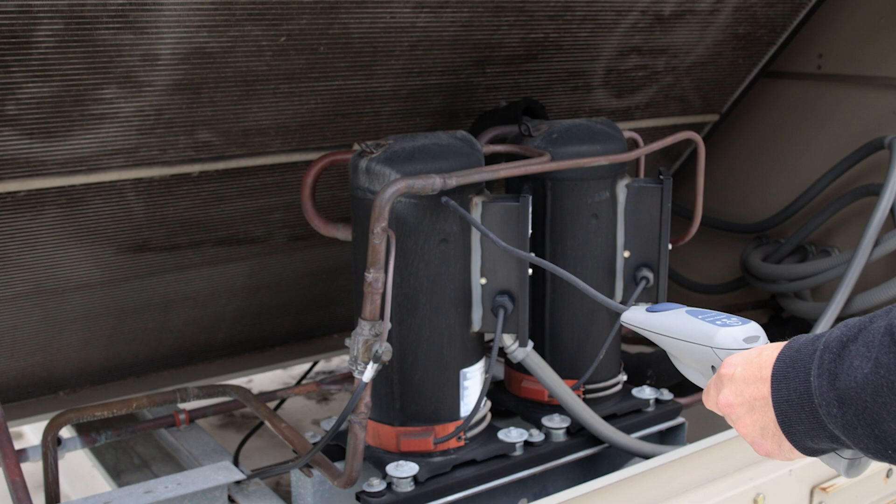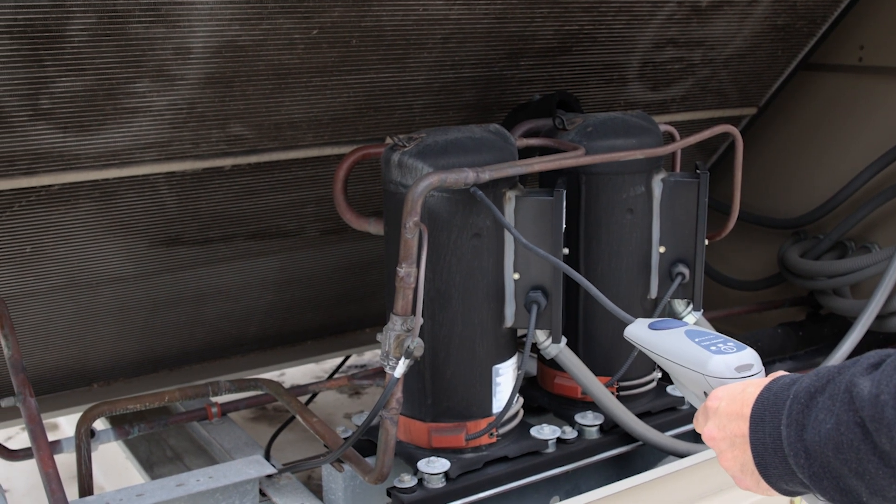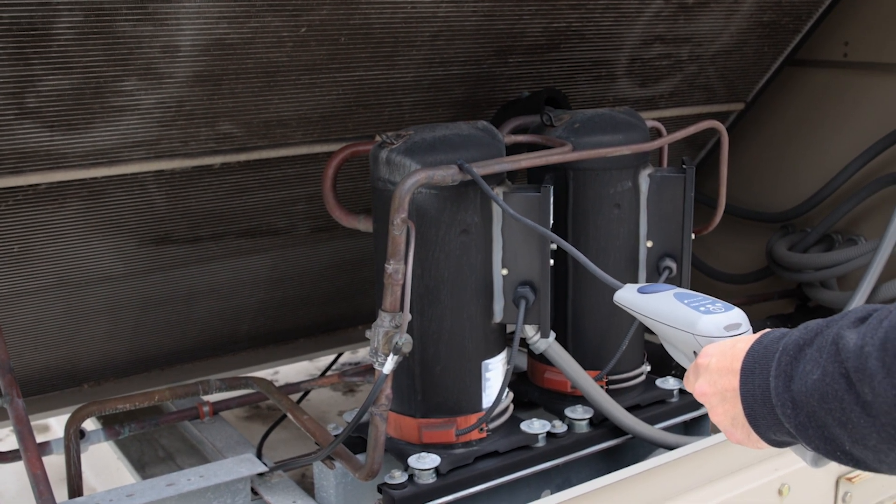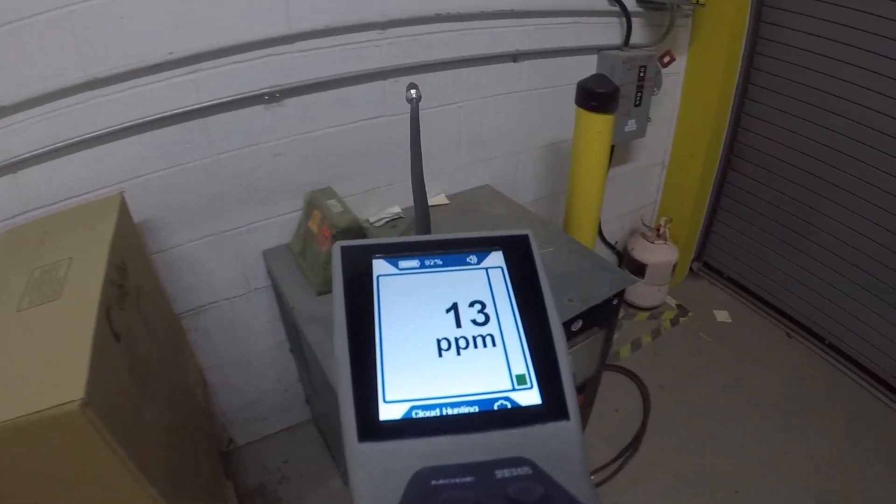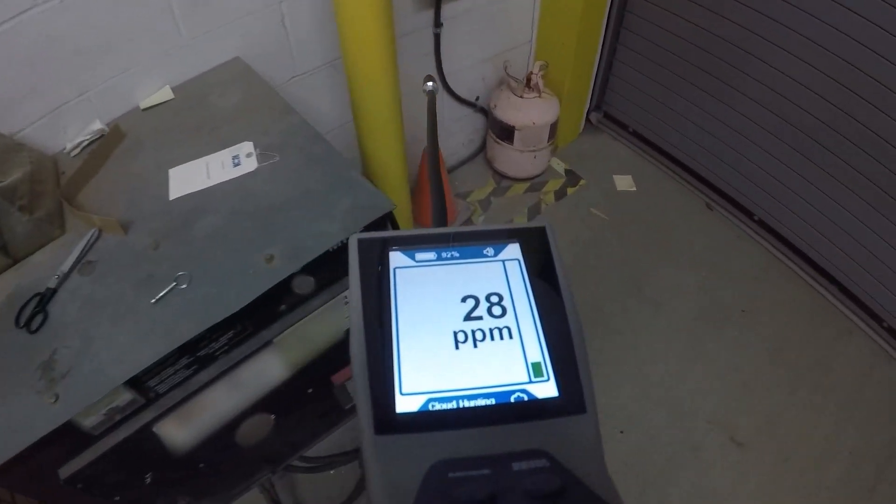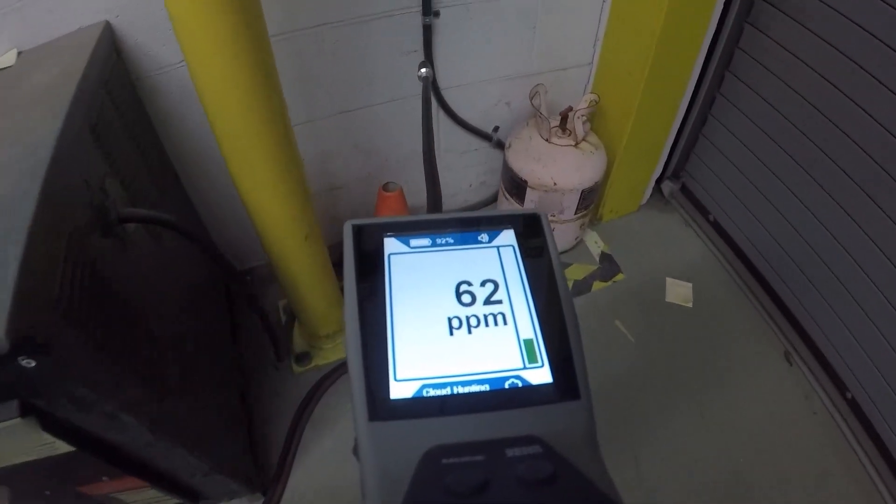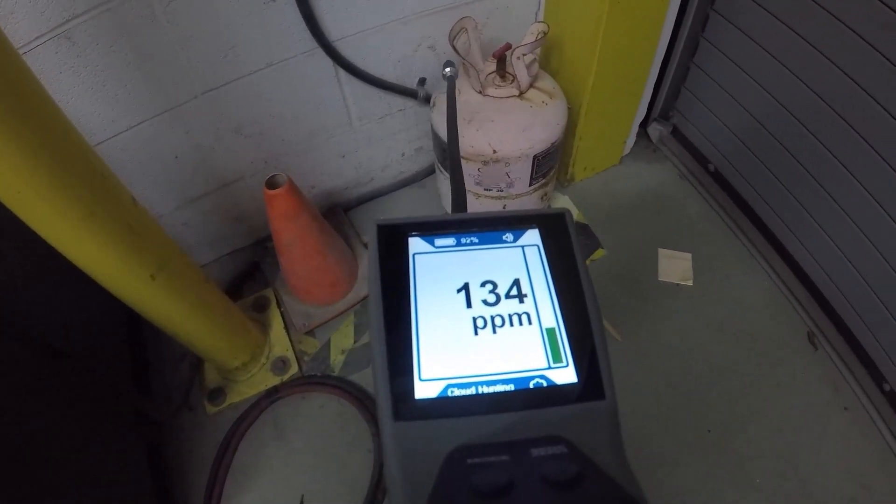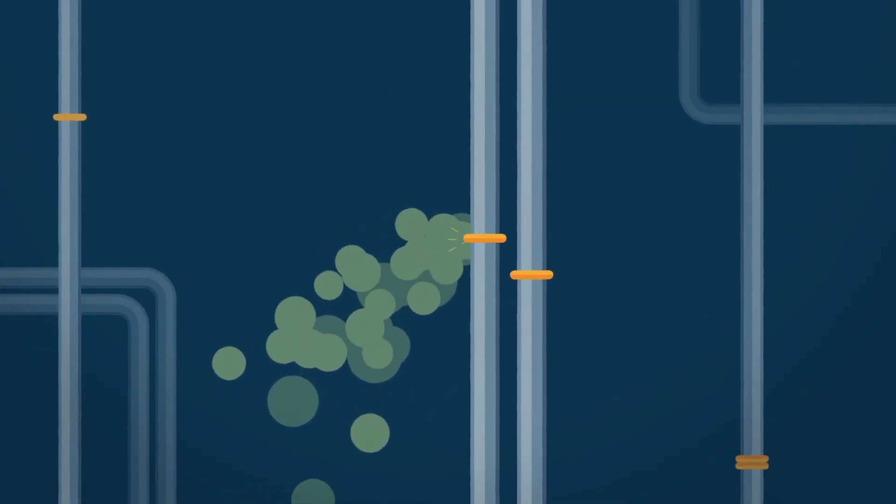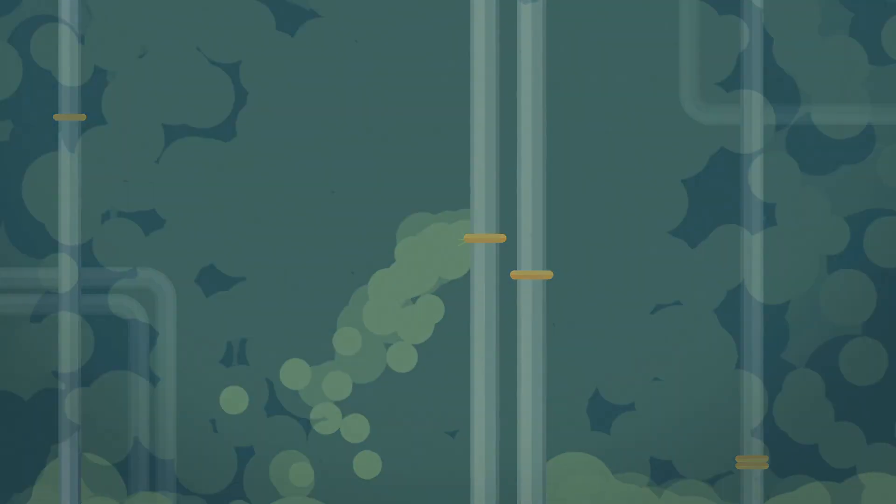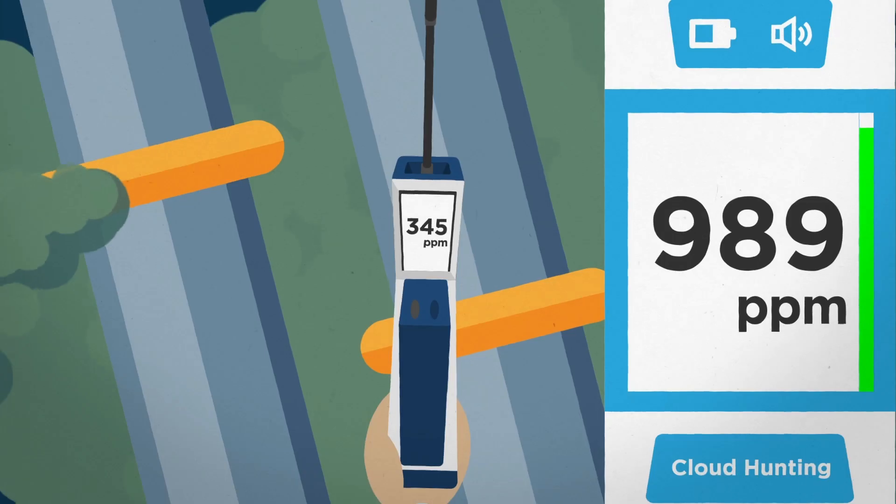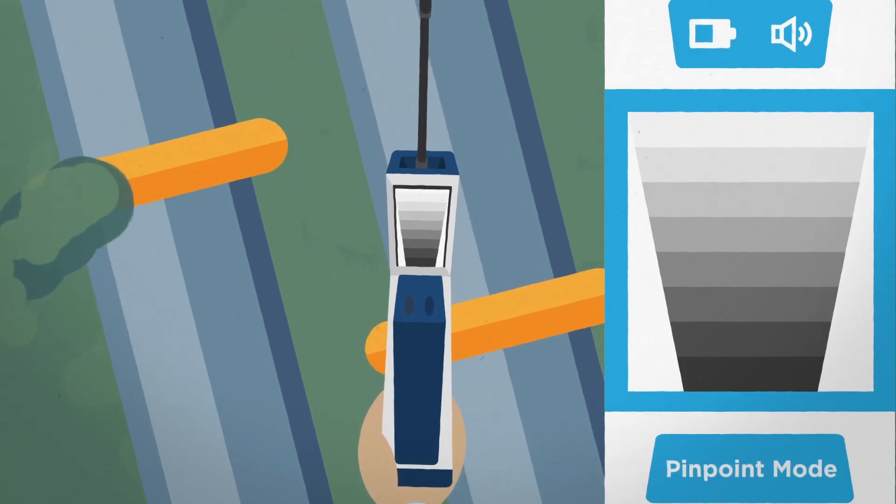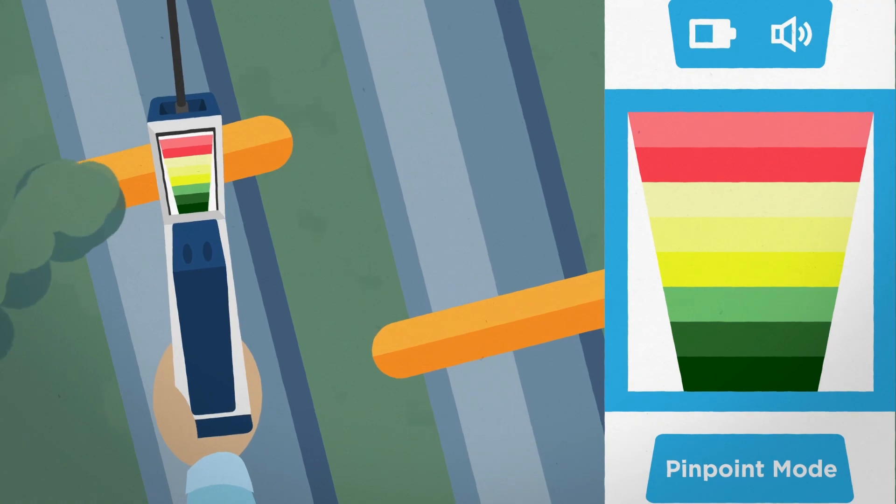While traditional sniffer leak detectors are great for finding most refrigerant leaks, there are some things they can't do. A traditional leak detector pulls in an air sample to identify if refrigerant is present, which means that the system must still have refrigerant leaking out, and there must be refrigerant where the leak detector probe is sampling. If the system is empty, or if you want to leak check a line from a distance, this can create a problem.